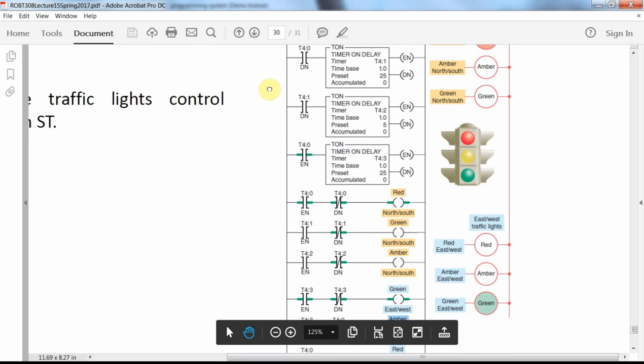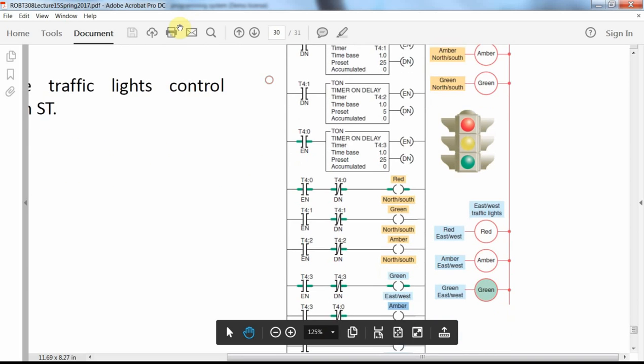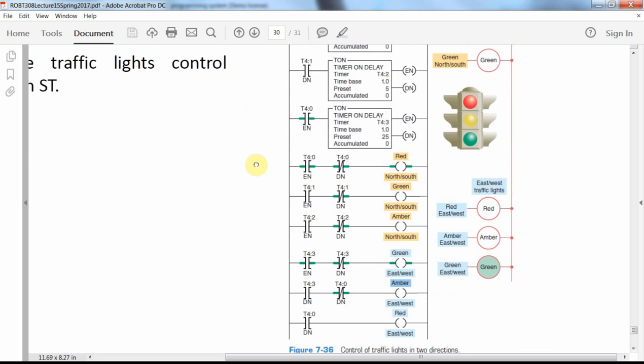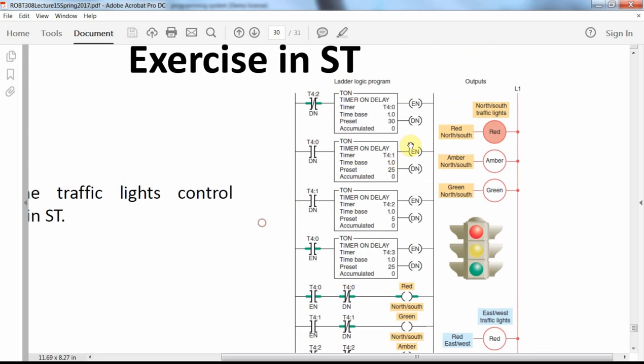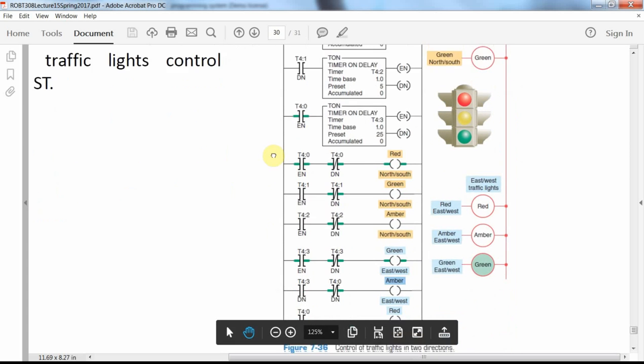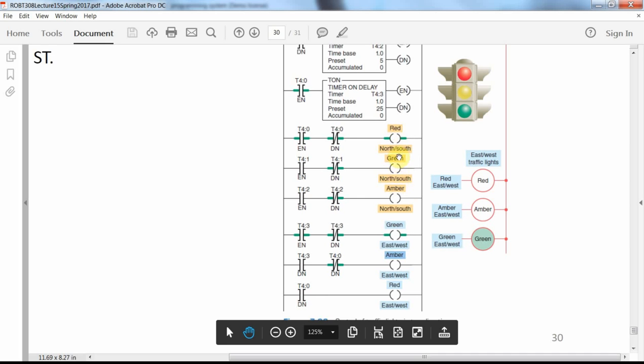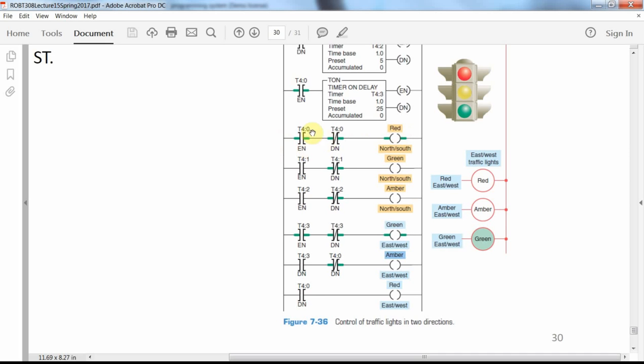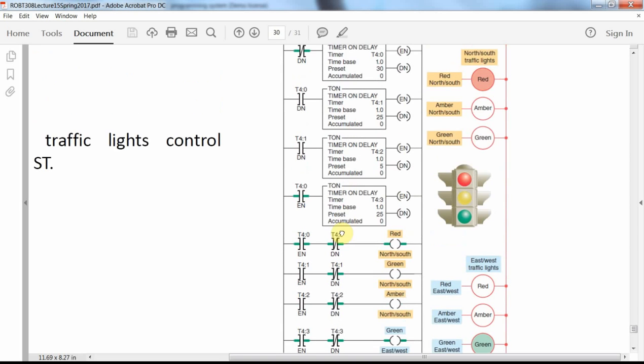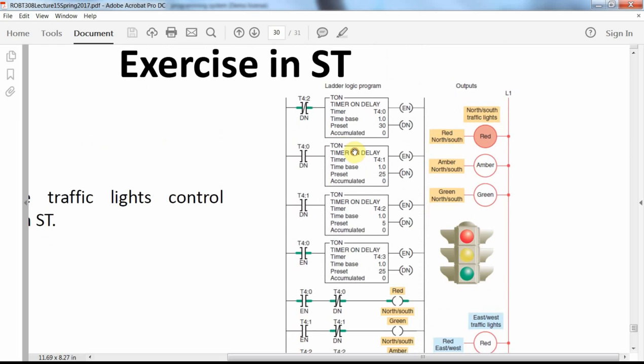You can see how the system is implemented using ladder logic diagram elements. We are using four on-delay timers with different preset time values, and they are receiving inputs from each other. To determine the state of the output pilot lamps in each direction, we use a combination of the enable bit and done bit of different timers.